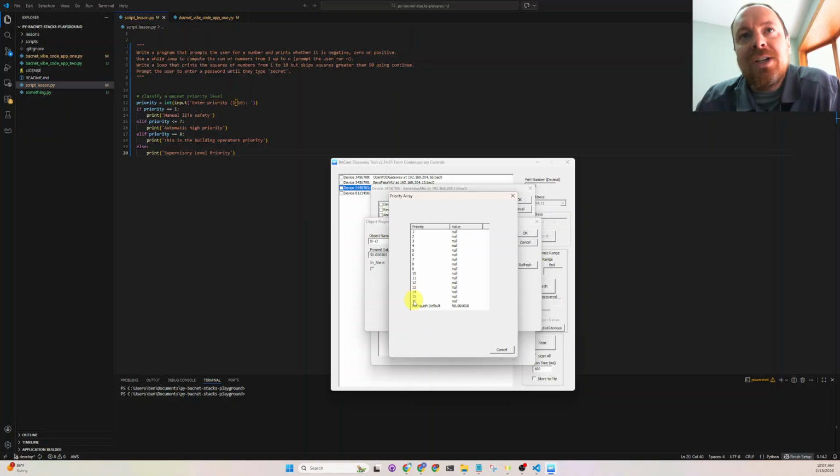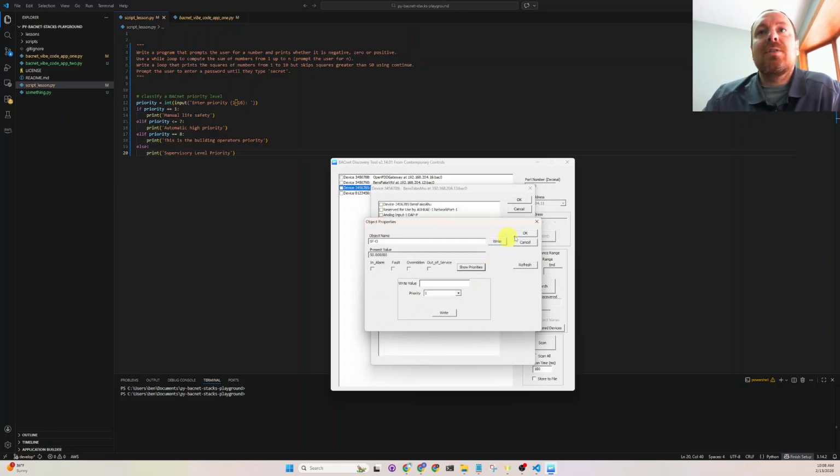It could come in down here somewhere, and somewhere in this lower range optimization also happens, where if we're optimizing in Python scripts outside of the BAS or on the BAS itself, we'll be down here, 9 through 16 somewhere. Then if the building operator needs to override it because the optimization is causing problems in the building, the priority 8 will be able to override anything down here. So hopefully that makes sense. So this is how that works in the real BACnet application.